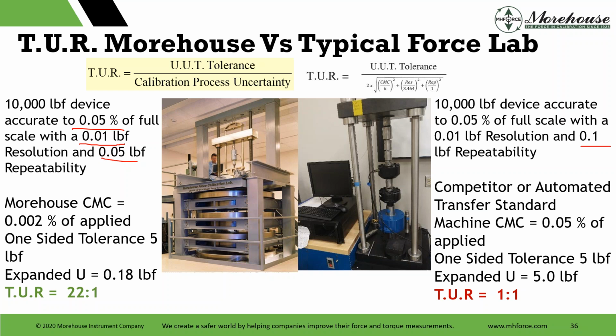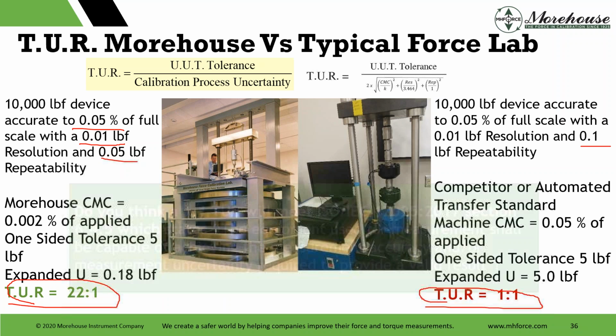The repeatability in a system, the lower my uncertainty, the better typically I can know my measurement. And the more plumb, square, rigid a machine is with low torsion, the better the repeatability. So here at Morehouse, just look at CMC of 0.002% of applied. This same load cell, 2 different labs. One lab, secondary standards, has a TUR of 1:1. That comes to Morehouse, it's 22:1.